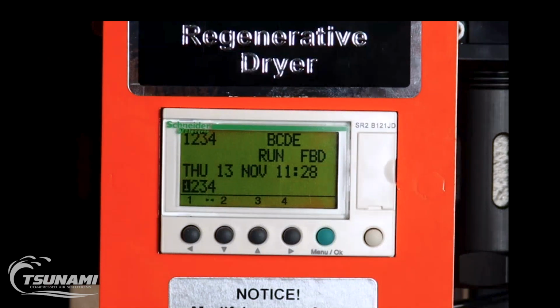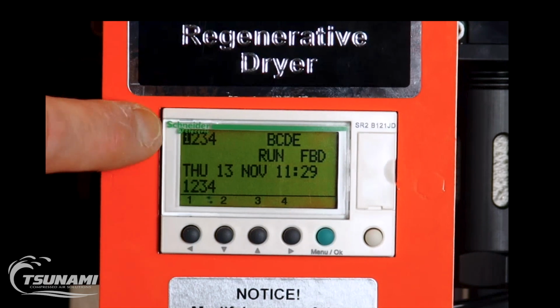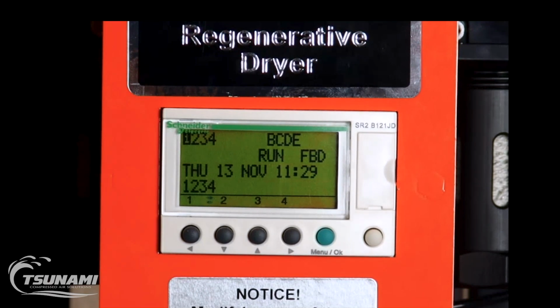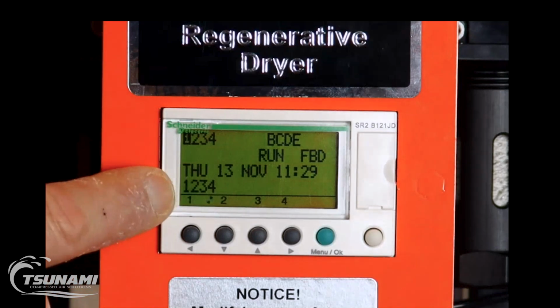So if we're functioning off of a digital signal, that would be some sort of dry contact that we're connecting from a piece of equipment, whether it be a CNC machine or a laser or a compressor. As long as we know that no air is going to be pulled through the dryer for use when those signals are being sent, that is exactly how we maximize the efficiency of the drying systems. So the first thing I'm going to do is flip one of those switches, and you can see the digital input 1 has turned on. And because the PLC received an input, notice that it paused the cycle.